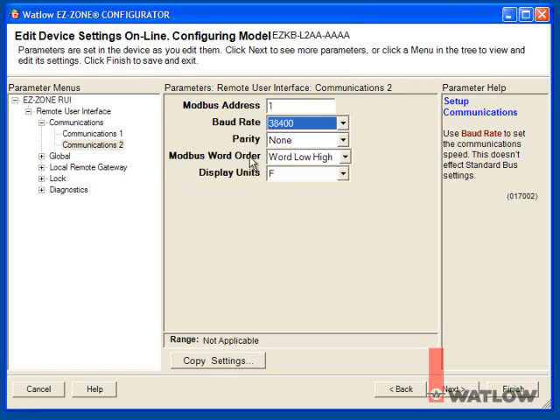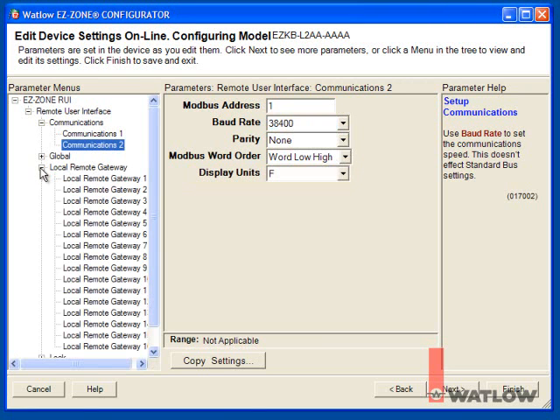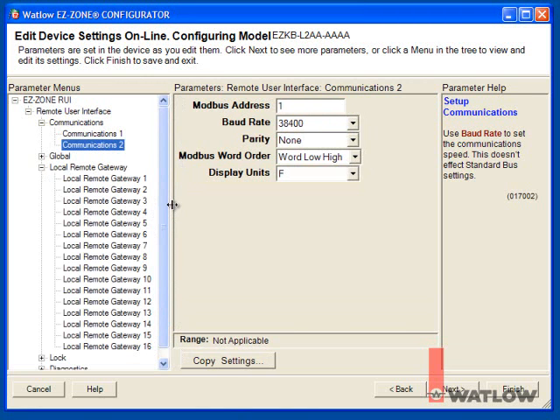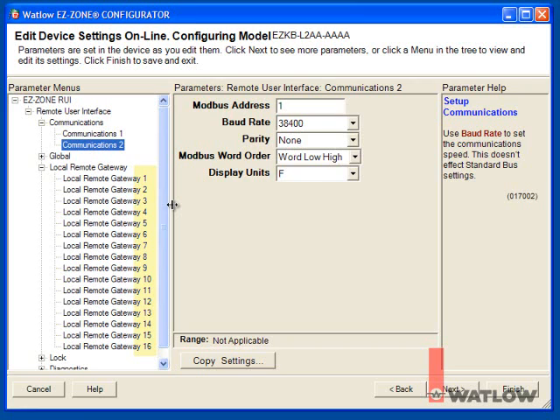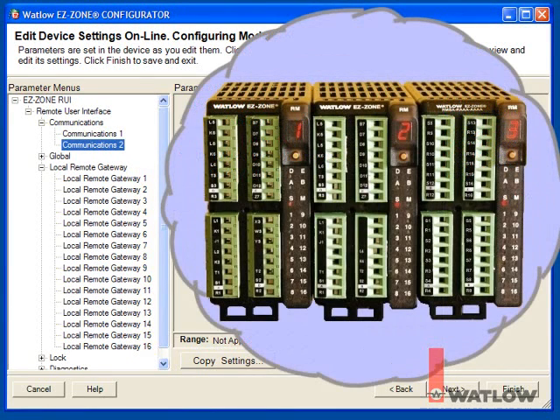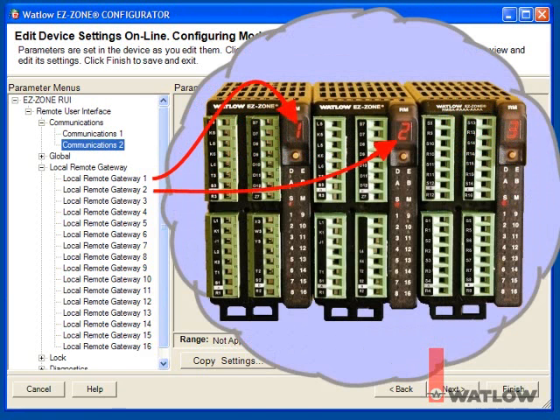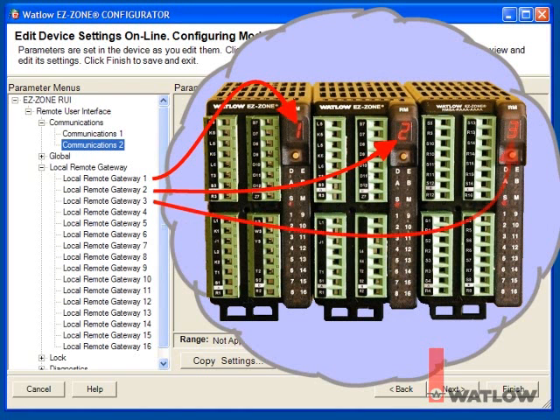An RUI Gateway or an RM Access Modules Gateway can connect up to 16 other EZZone devices such as RM Control Modules to a Modbus RTU network. The Gateway function is enabled and configured using the Local Remote Gateway Menus. The Local Remote Gateway Instance Numbers correspond to the standard bus addresses of the connected EZZone Modules, so the connection to the RM Control Module with address 1 is configured on the Local Remote Gateway 1 menu. The second RM Controller's connection is configured on the Local Remote Gateway 2 menu, and the RM Scanner's connection is configured on the Local Remote Gateway 3 menu.